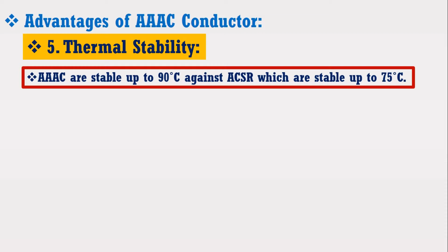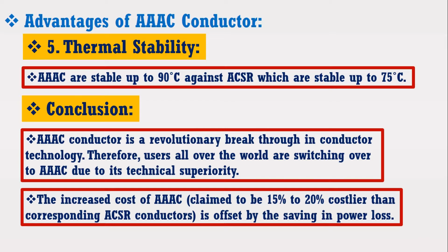In the nutshell, it may be concluded that all aluminium alloy conductor is a revolutionary breakthrough in conductor technology. Therefore, users all over the world are switching over to all aluminium alloy conductor due to its technical superiority. Only disadvantage of this conductor is its high cost compared to ACSR conductor. However, this increased cost, claimed to be 15% to 20% costlier than corresponding ACSR conductor, is offset by the saving in power loss in the long run.